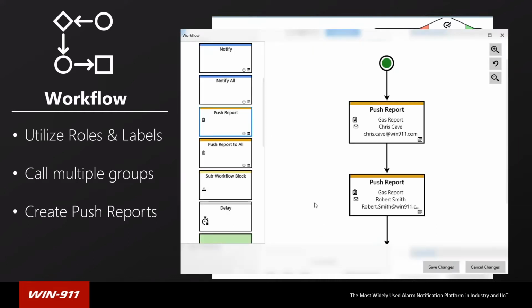And then we have push reports. So push report is a way of automating a report. This is where you would assign some sort of bit that would toggle at a certain time every day. When that bit triggers, we see it come into WIN-911 as an alarm, but it's not technically an alarm. And we tell that alarm to trigger this advanced workflow that's basically just pushing out a report to someone. So you could have that turn on maybe every hour, every 30 minutes to push those reports to people if you'd like.